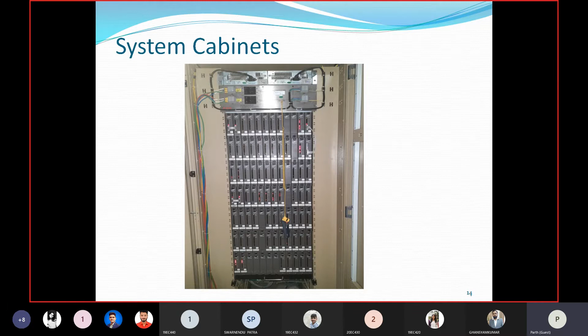Now the question comes, we have different types of control, some analog control, some digital control. We have a transmitter, we have an RTD. So we have different types of modules designed. You can see here analog input module, analog output module, digital input module, and digital output module. What will these different types of modules do? Each module will generate the data as per the requirement. Analog output module will generate only 4 to 20 milliampere. Analog input module takes 4 to 20 milliampere from the field. Digital input module will take the contact of a relay, and digital output module generates a signal and actuates the relay. So these are the different types of modules used in Harmony hardware or any control system.